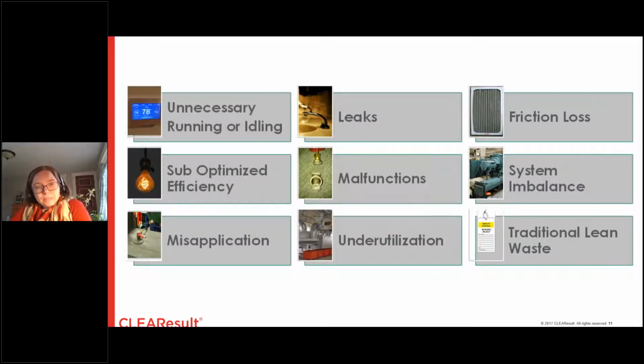A system imbalance. So we're all the way over on the right, one down. System imbalance is anything that's operating at some kind of peak design worst case scenario, and most of the time it's not peak design worst case scenario. So think of maybe a VFD that's been overridden and it's operating at 100% because there was some kind of incident and somebody thought they needed full flow and they never came back and undid it, right? You might be seeing full flow and you don't need full flow. This could be, say, a programmable thermostat that's been overridden or never scheduled, right? So overnight, your HVAC system is aggressively targeting an occupied set point and it doesn't need it. It's not a design occupancy or a design loading condition, right? So beware of those system imbalance moments.